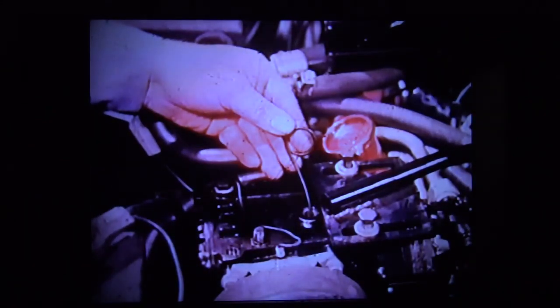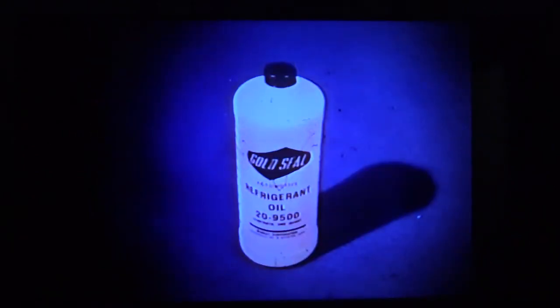Remove the oil filler plug and insert a 1/8 inch diameter steel rod through the filler hole until it bottoms in the compressor crankcase. Remove the dipstick, measure the wetted portion, and compare it with the correct oil level specification. Add or remove oil until the correct oil level is obtained. If oil must be added, be sure to use only the proper refrigerant oil designated for that compressor. Consult the latest edition of your air conditioning service manual for oil specifications.